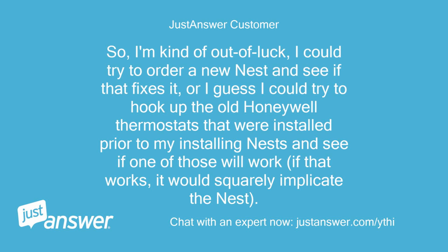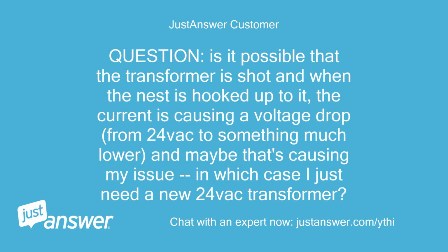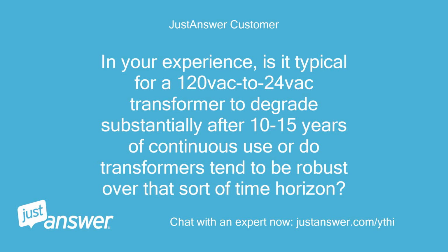I could try to order a new Nest and see if that fixes it, or I guess I could try to hook up the old Honeywell thermostats that were installed prior to my installing Nests and see if one of those will work. If that works, it would squarely implicate the Nest. Question: is it possible that the transformer is shot and when the Nest is hooked up to it, the current is causing a voltage drop, from 24 VAC to something much lower, and maybe that's causing my issue, in which case I just need a new 24 VAC transformer? In your experience, is it typical for a 120-vac to 24-vac transformer to degrade substantially after 10 to 15 years of continuous use, or do transformers tend to be robust over that sort of time horizon?